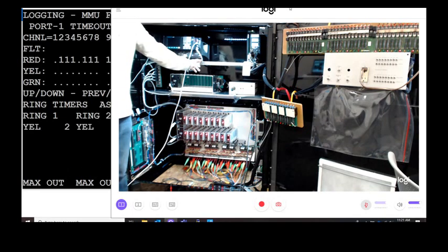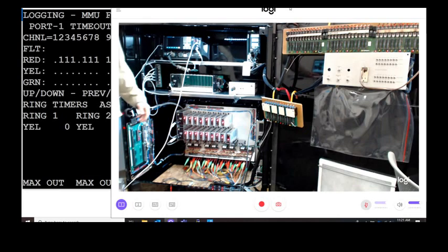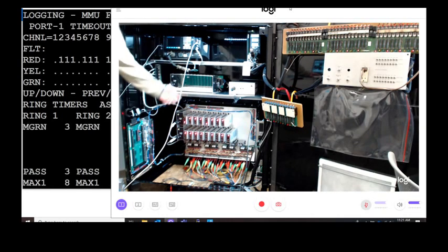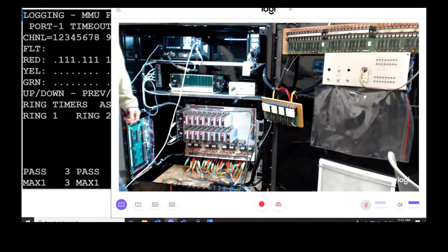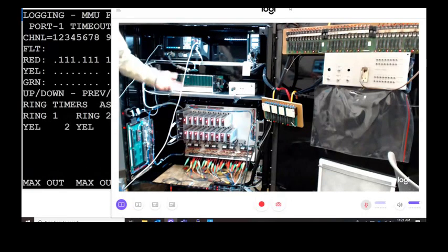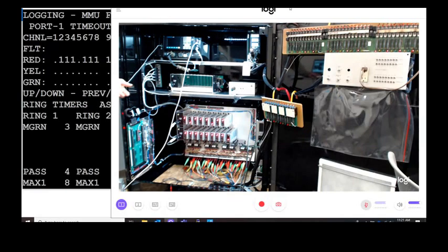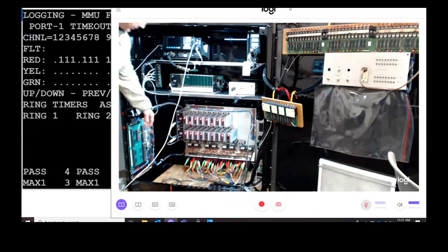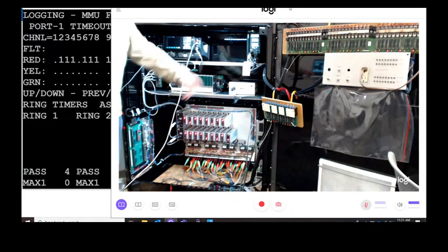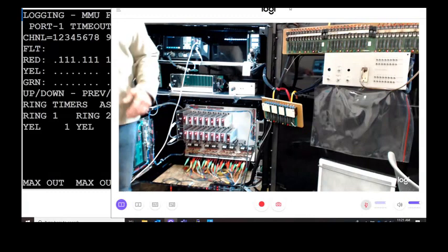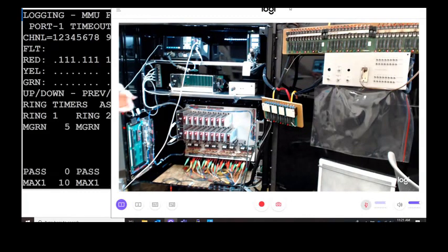This SDLC bus basically has, I think, 18 volts on it. So anything over 18 volts, a lot of times we were seeing, before we went to a lot of different suppression, during hurricane season. Once we start getting into late summer and early fall, the hurricanes come through, the high winds, a lot of the lightning, it would get onto the cabinet and basically get onto this bus. And that's when you would see each BIU get blown out, maybe a controller, maybe an MMU. It became a $5,000 or $6,000 repair to replace all those components.